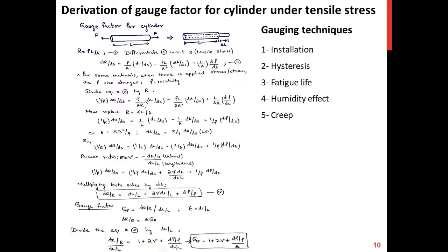As there is continuous use of the gauge during operation, its stresses can be avoided by not increasing the load factor beyond its range, that is, by not increasing the strain beyond certain limits, and also by preventing faulty bonding between the gauge and the loading surface. And the third one is fatigue life. Fatigue life often arises due to the stress reversal occurring at the leads of the gauge and causes decay in the backing of the gauge.